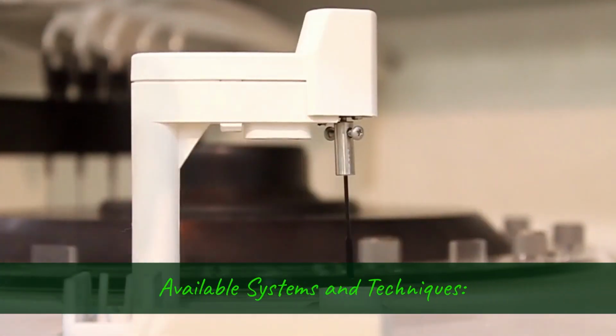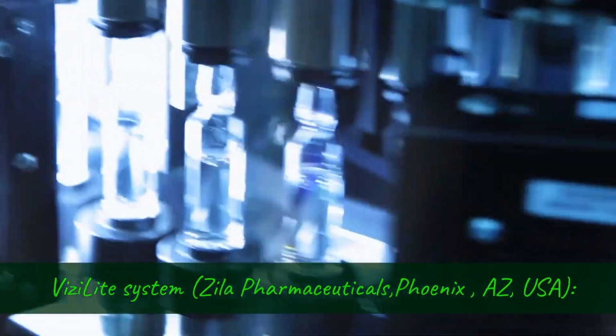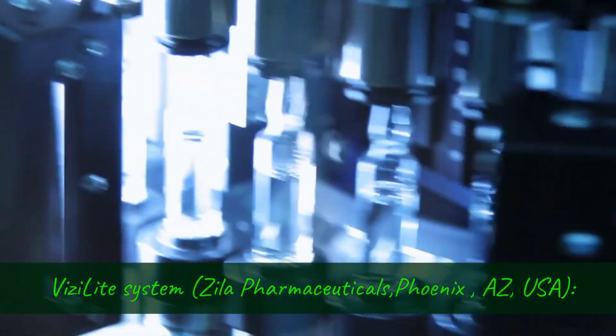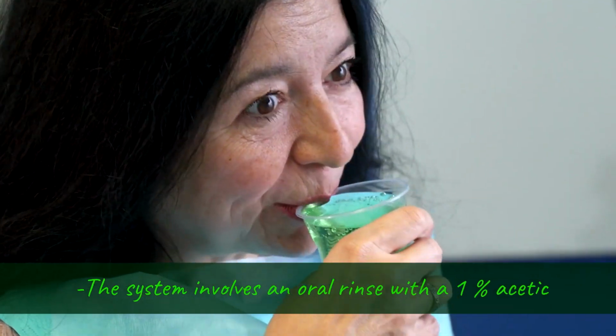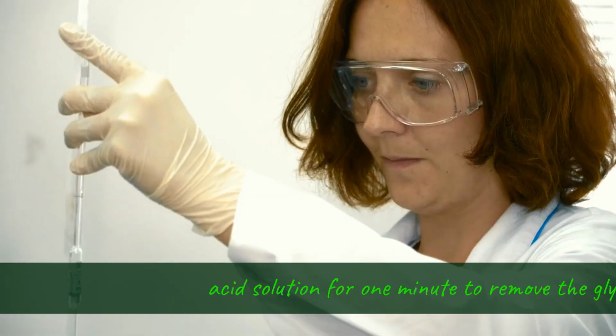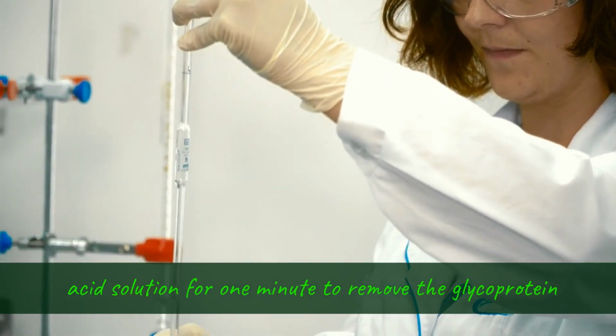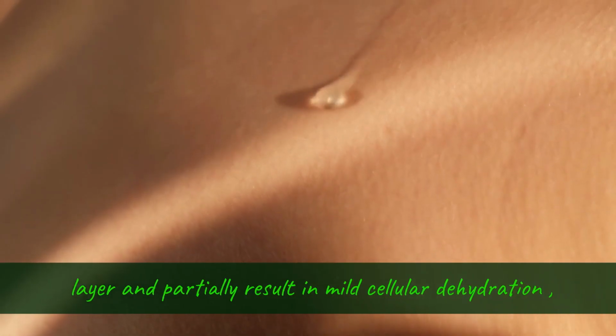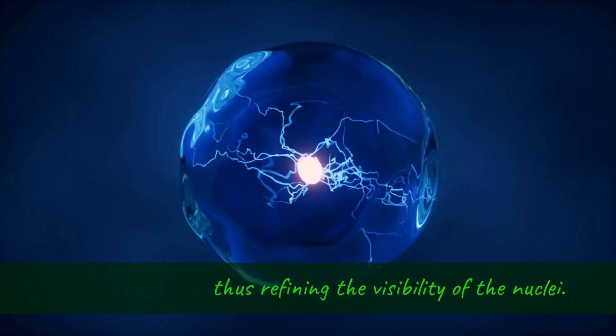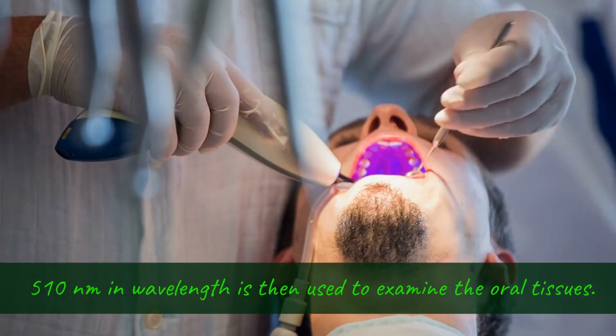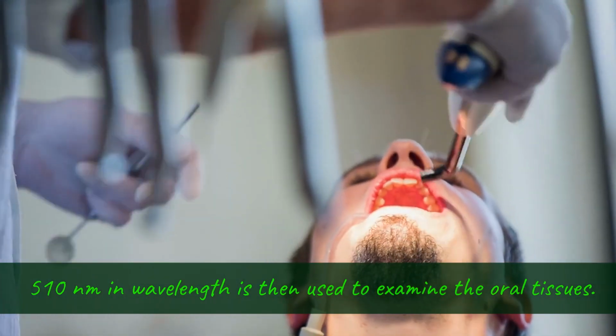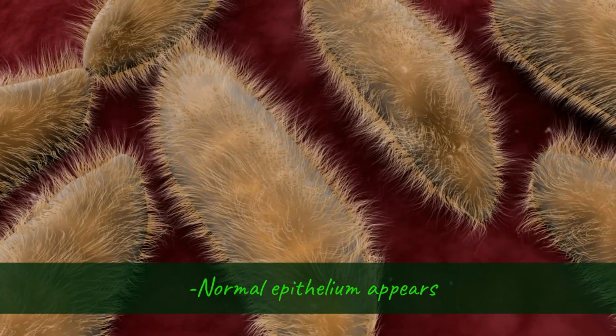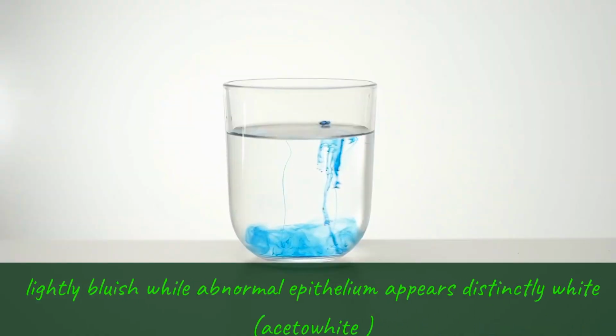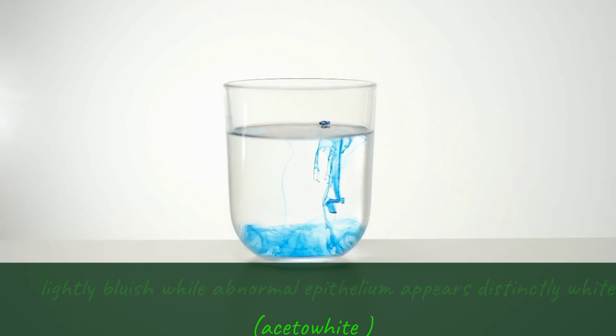Available systems and techniques. ViziLite System, Zila Pharmaceuticals, Phoenix, Arizona, USA. The system involves an oral rinse with a 1% acetic acid solution for 1 minute to remove the glycoprotein layer and partially result in mild cellular dehydration, thus refining the visibility of the nuclei. A handheld device emitting blue/white light of 490-510 nanometers in wavelength is then used to examine the oral tissues. Normal epithelium appears lightly bluish while abnormal epithelium appears distinctly white, acetowhite.